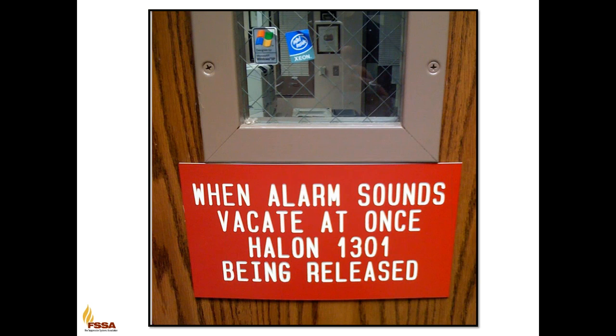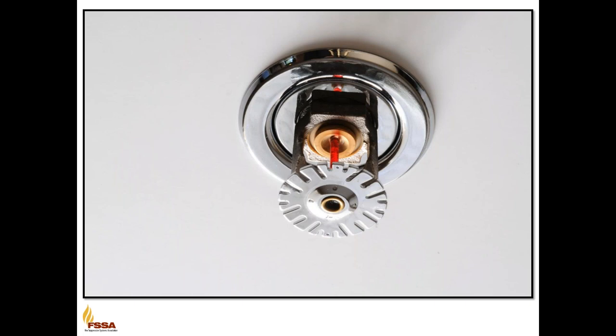For one, Halon 1301 was the fire suppression agent of choice for the type of environment such as the Hinsdale facility, although that particular switching station did not have a Halon system at the time of the fire. Had the Hinsdale facility been equipped with a Halon system, we probably would not be talking about it today.